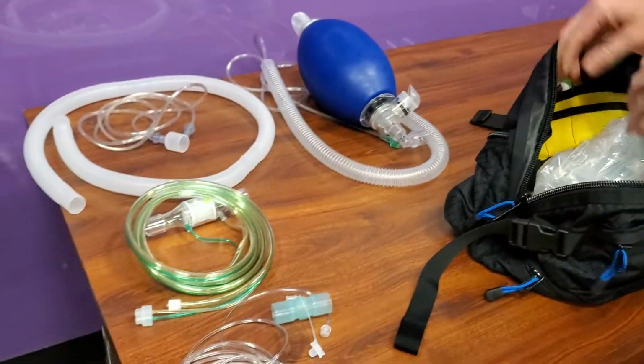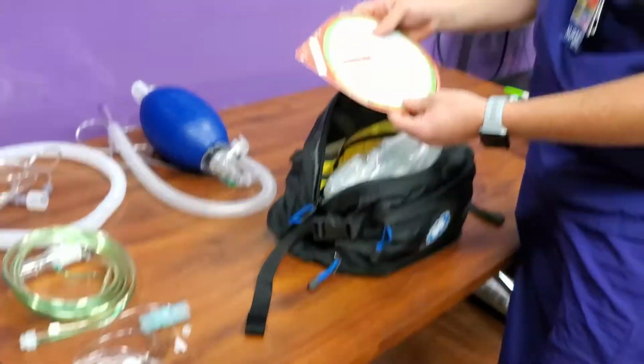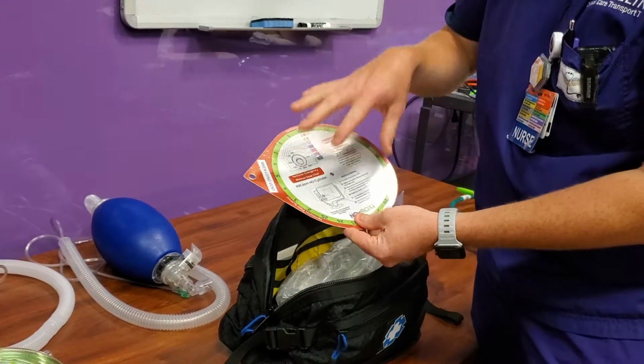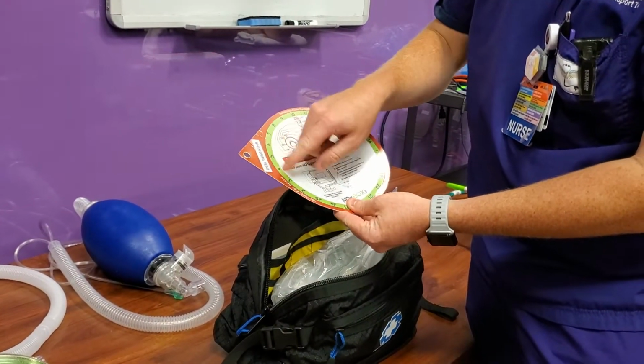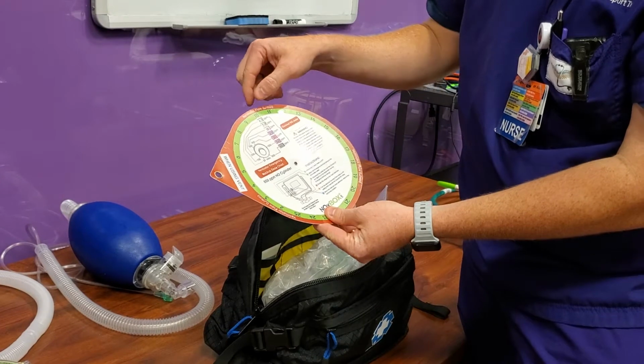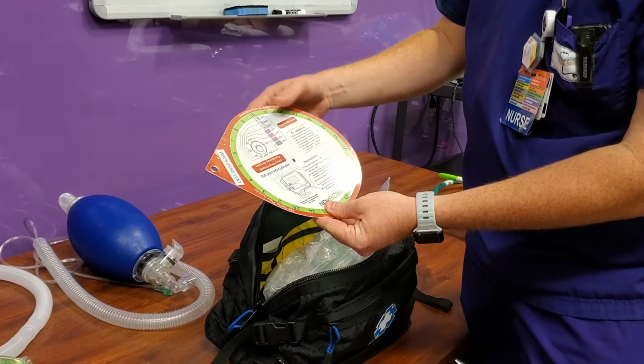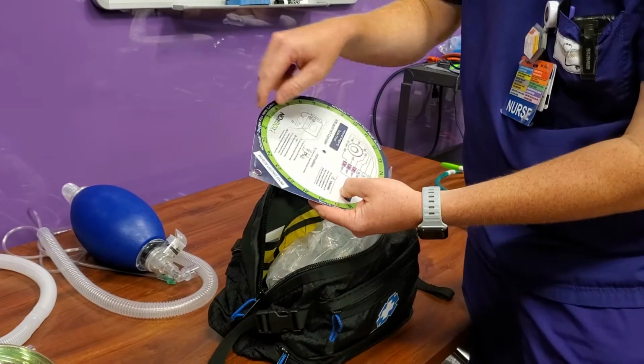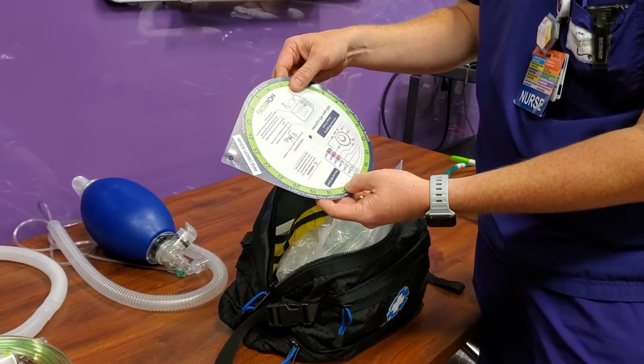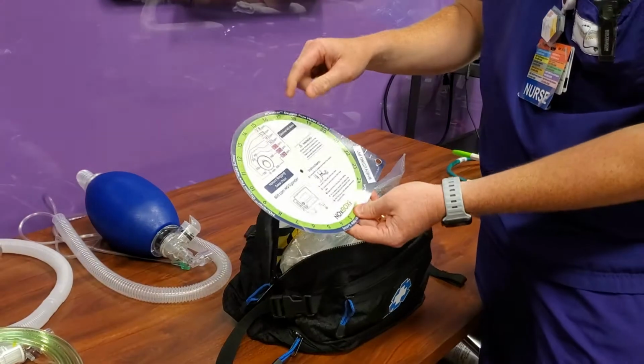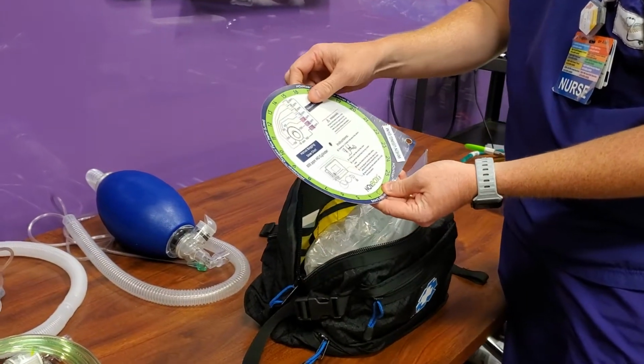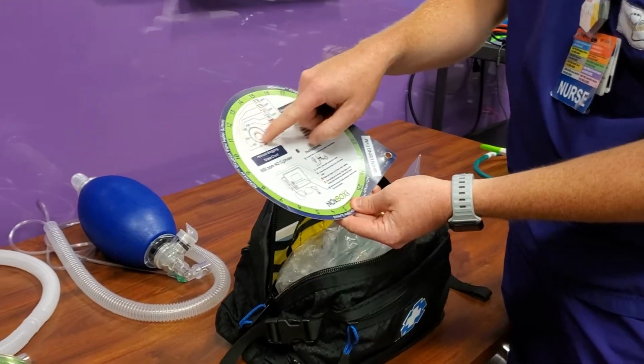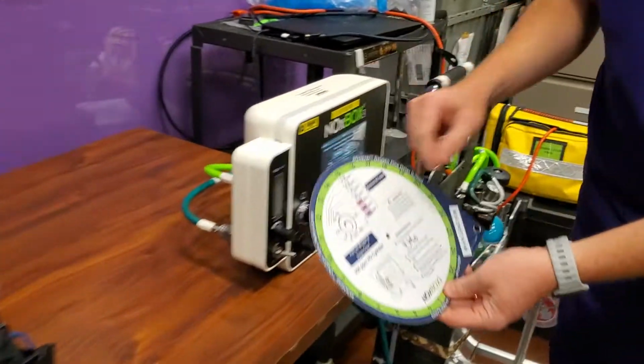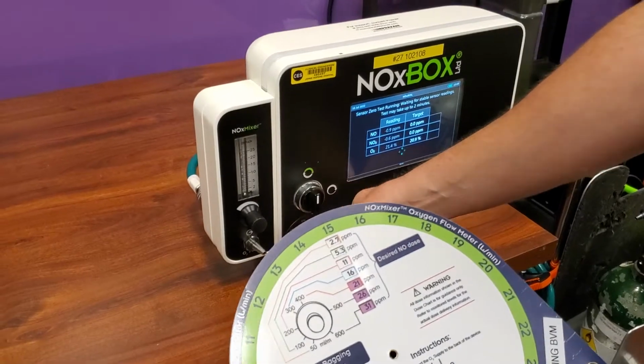We also have in here our backup wheel if you do need to use your flow sensor. Red side is for when you're using the ventilator, and this green circle is going to be your minute ventilation, what the patient's currently pulling. Our other side here is the blue side, and this green circle is what you are setting your BVM to. Most people obviously set it to around 15, so you just set it to whatever you need there, and then you can base your concentration off of your dial on here.